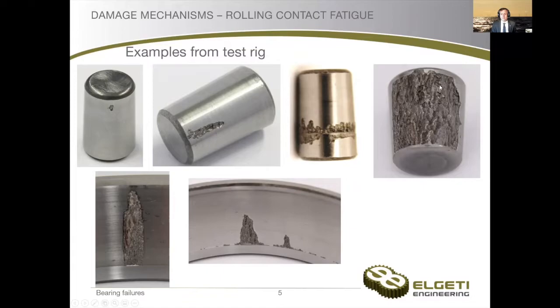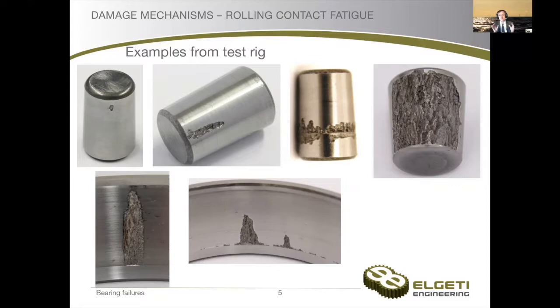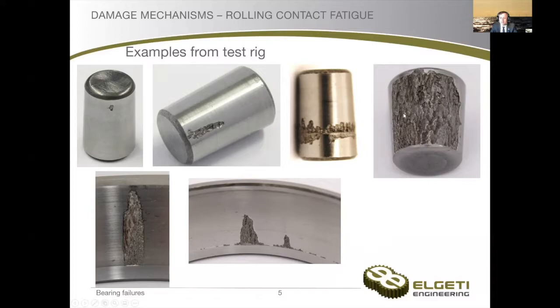The cracks will first propagate parallel to the surface until complete flakes leave the raceway. This leads to a very characteristic pattern. You can see this here — these are some examples that we produced in our bearing test rig, where we know very well what happened. This is basically the smallest kind of flaking, the smallest pitting that we can possibly have just because of this failure mechanism. The cracks propagate parallel to the surface; nobody will notice them until a complete flake leaves the roller. If the flaking starts at one position, the propagation is first in the axial direction until the complete raceway width is utilized, and then it goes further around the circumference.